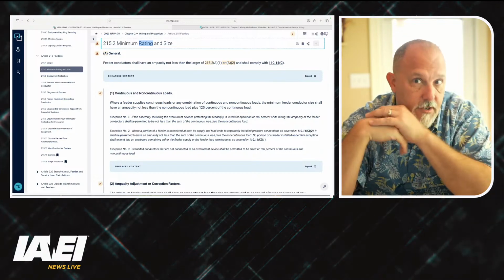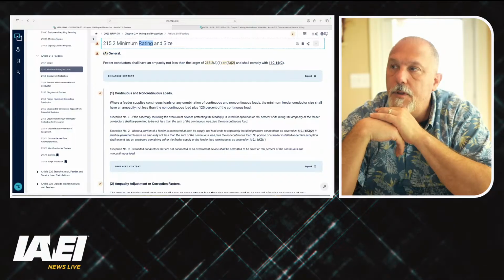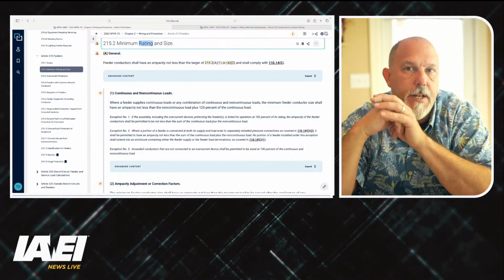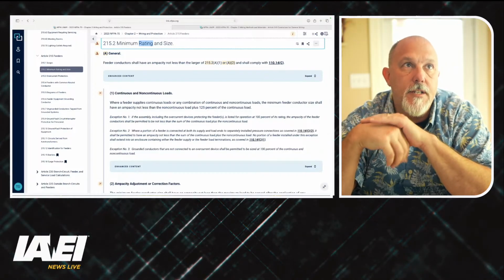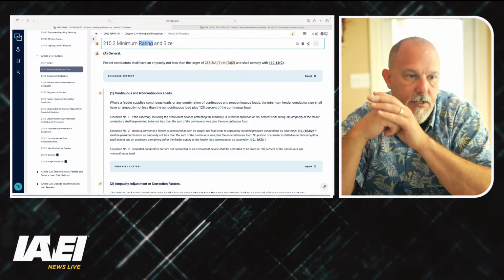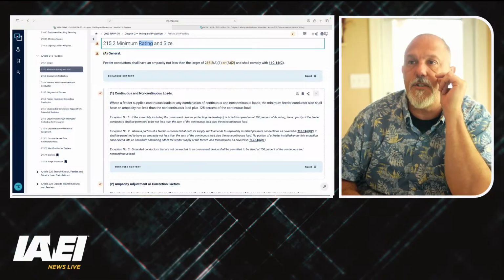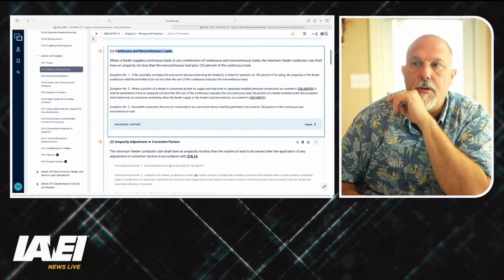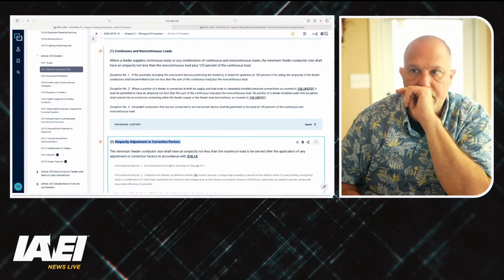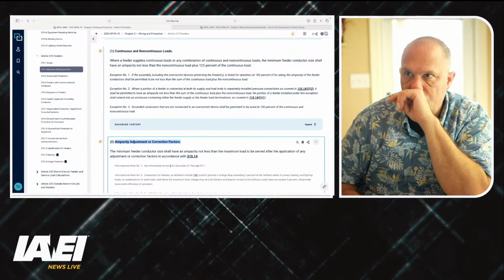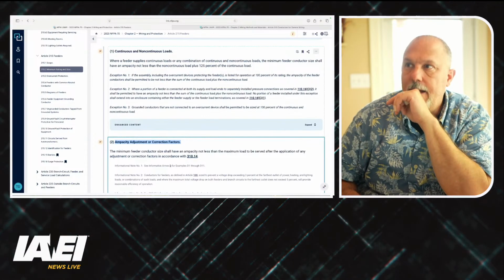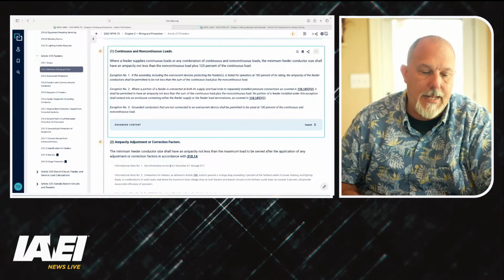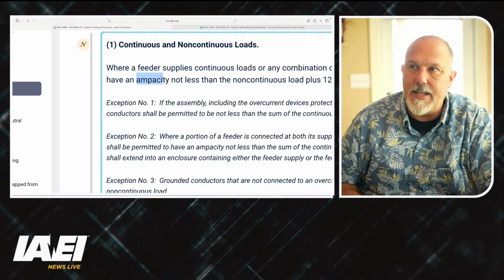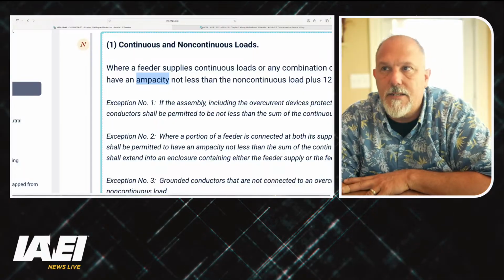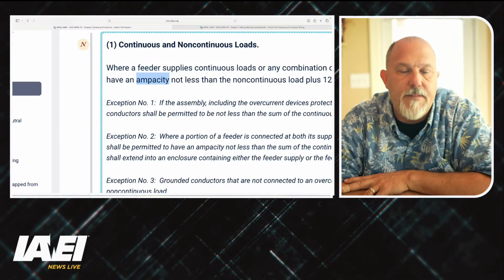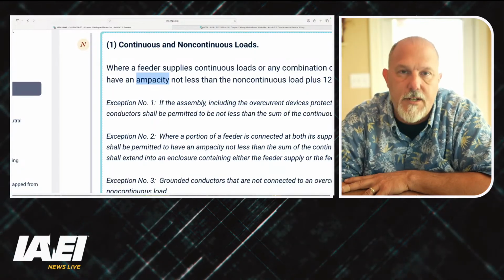Feeders serve multiple branch circuits. So there's probably a little bit more work that has to go into determining all of the loads on a feeder that are continuous and all of the loads on that feeder that are non-continuous. All right, but it's the same process. 215.2, you have your continuous current loads, and you have your ampacity and adjustment corrected factors. And this was the word that during this past cycle, shall have an ampacity, and that's wrong. That's not right. And hopefully we can fix that this cycle. That should not say ampacity.